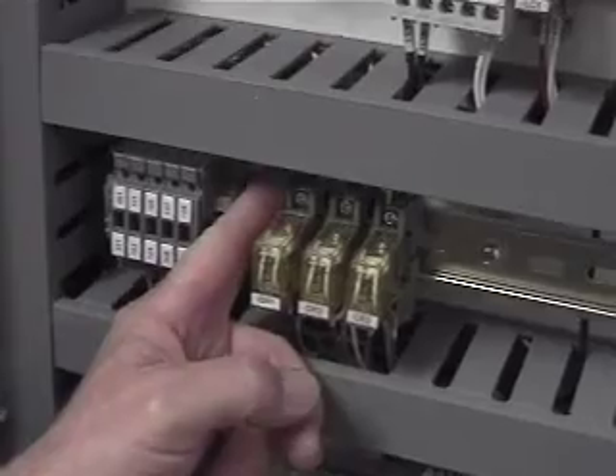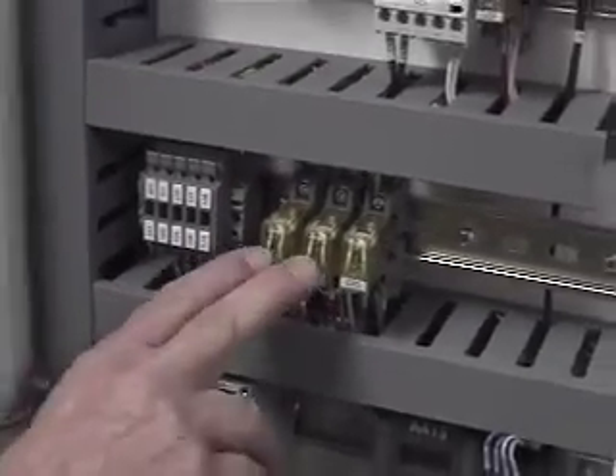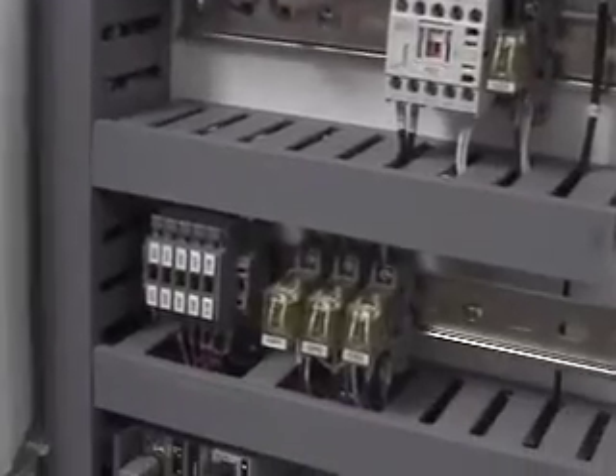Right now in the controller they're set up as normally open, but we run our alarm relays normally energized. So as long as there's no problem, they are energized, and they de-energize on a fault. You can actually change the polarity of them if you want to, just by moving this wire down. But for right now, you'll have a normally closed in normal operations. It'll open if something happens. We do that because if you lose power, obviously your alarms aren't going to tell you anything. So if you lose power, it'll switch the state of the relay, and you have a change.